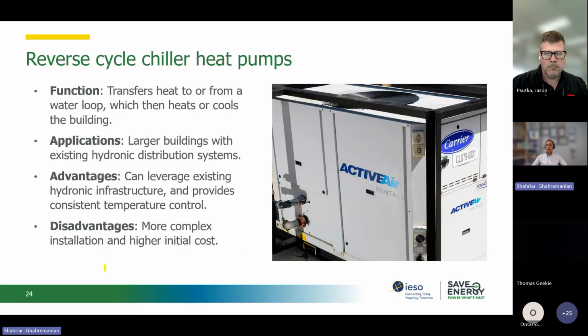Then we go to the reverse cycle chiller heat pumps actually. Again, these are good for larger buildings with an existing hydronic distribution system. So basically they transfer heat to or from a water loop actually, and then either heat or cool the building actually. So again, similar to that recovery system that you saw, this is a reverse cycle chiller heat pump. So these are good also, but the only thing is that we need to have a hydronic infrastructure, and this is a good one. But again, this needs an engineering design. It has a complex installation, and the initial cost compared to the split system can be higher actually.